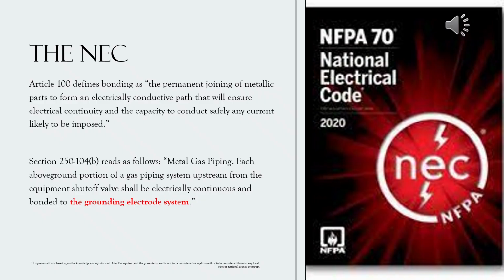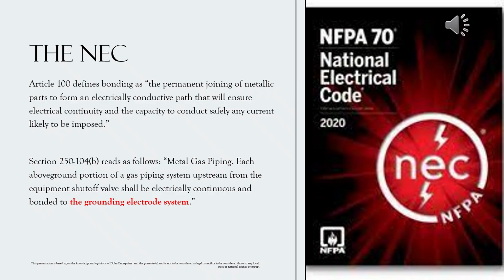Article 100 defines bonding as the permanent joining of metallic parts to form an electrically conductive path that will ensure electrical continuity and the capacity to conduct safely any current likely to be imposed. That's a mouthful. Section 250.104(B) reads as follows: metal gas piping. Each above ground portion of a gas piping system upstream from the equipment shutoff valve shall be electrically continuous and bonded to the grounding electrode system. So that's what our code says.